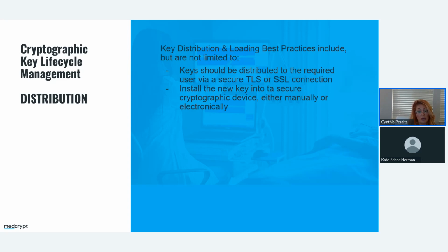The suitability of a particular key distribution scheme depends on the type of device, the expected interactions with other parties, and other assumptions about the operational environment. So, for example, if the programmer and the medical device will have a lasting relationship, a preset key can be used. The solution could be valid when the programmer is always a device belonging to the patient or the physician.